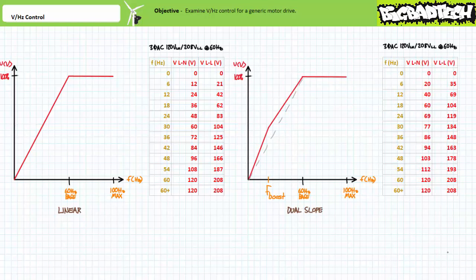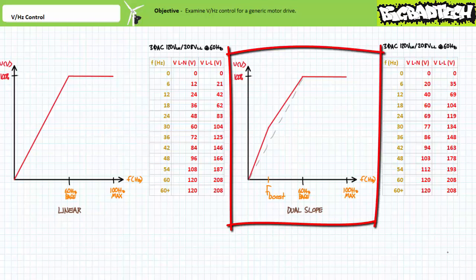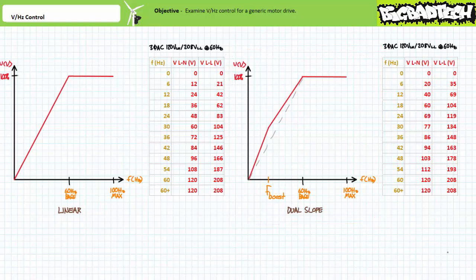Depending upon the features incorporated in a particular motor drive, other application-specific volts per hertz profiles may exist. Consider this dual slope increased torque or torque boost profile where applied voltage increases at a steeper slope up to a certain transition frequency, beyond which the slope decreases. Upon reaching the base frequency, full voltage is applied. Such a volts per hertz profile could be useful for a load with a large initial static inertia or friction. This dual slope volts per hertz profile has a notable knee defined by a point called the boost frequency, where voltages are boosted. The amount of boost voltage and the boost frequency value can be expressed directly or as a percentage above the normally linear applied voltage at base frequency, and both values are often user adjustable.